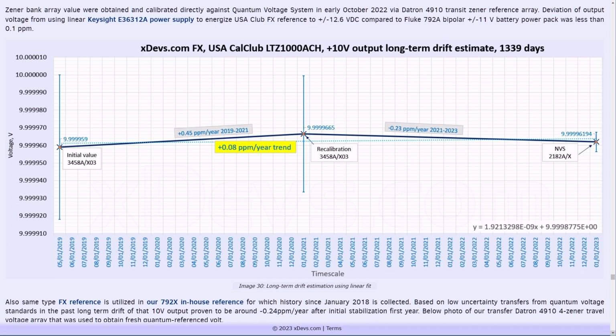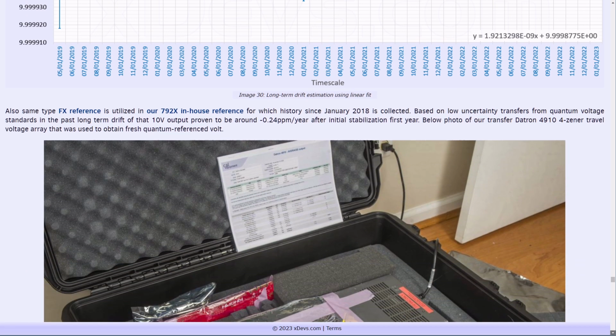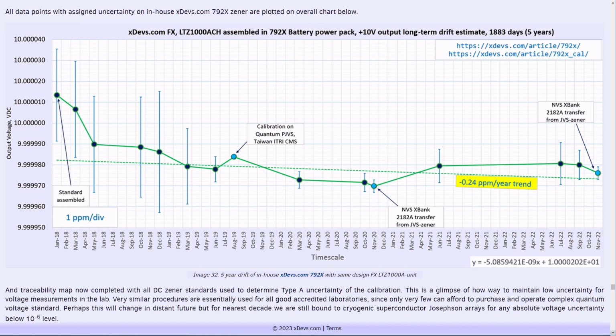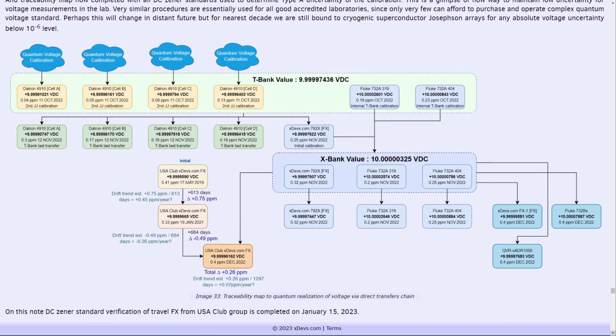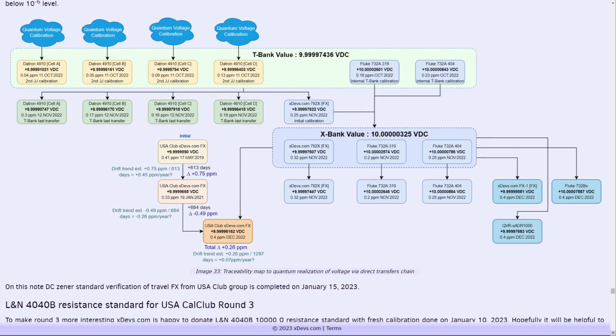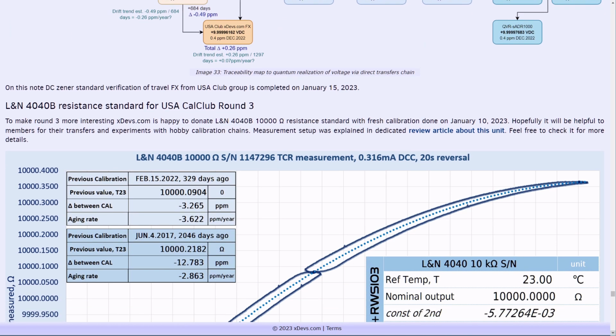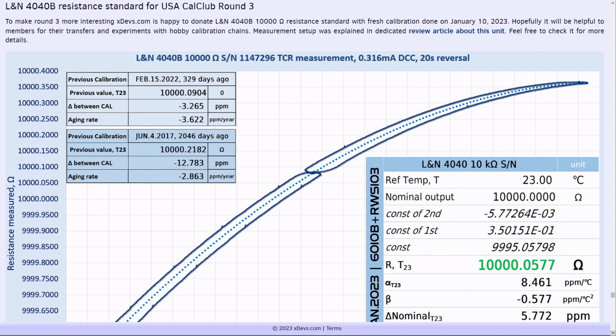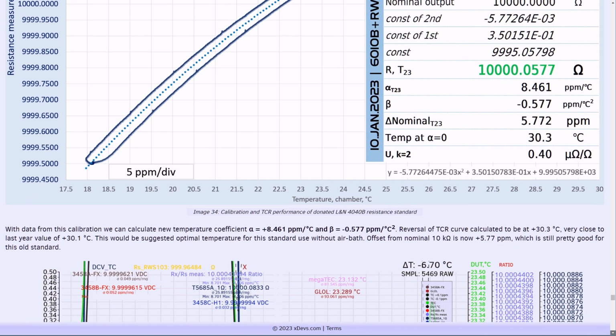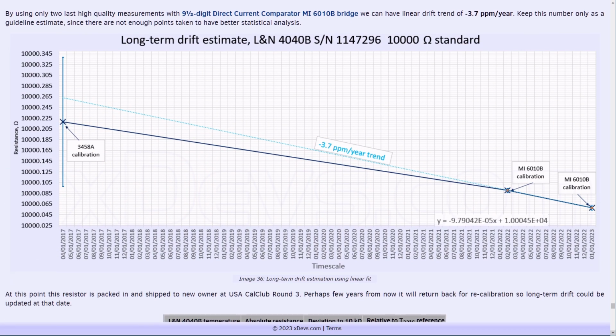Now you might ask, how can I ensure low uncertainty of all these DC voltage measurements? And the answer is presented below. Essentially, we used in-house FX reference and monitor it over 5 years time, as well as other commercial standards such as DATRON 4910 or Fluke 732A. DATRON 4910 was calibrated with a quantum voltage standard using direct measurement, actually 2 times, and by using this data we could estimate long-term drift of in-house zener standards, and that allowed low uncertainty for DC voltage measurements presented in this video and article. And the next item is 10 kilo ohm standard that I donated to USA CalClub.